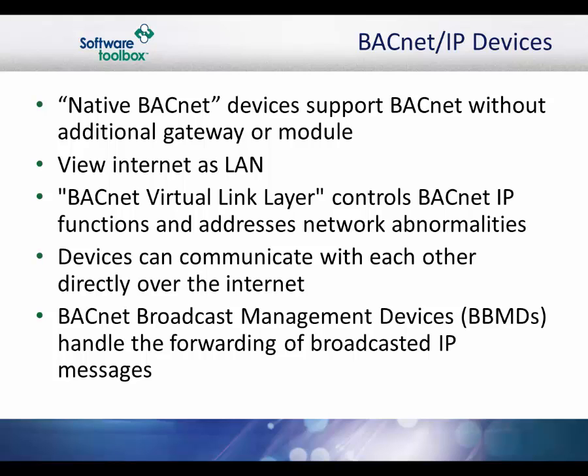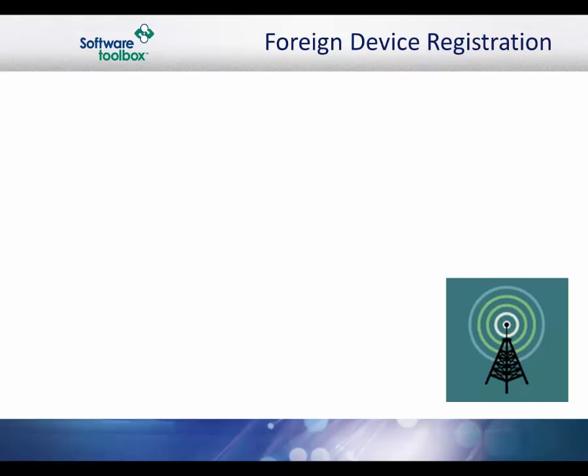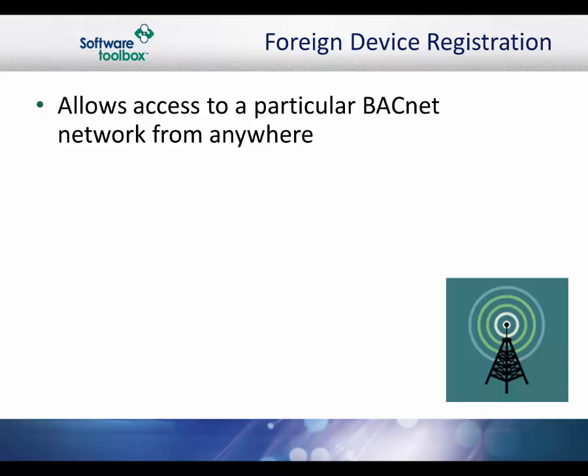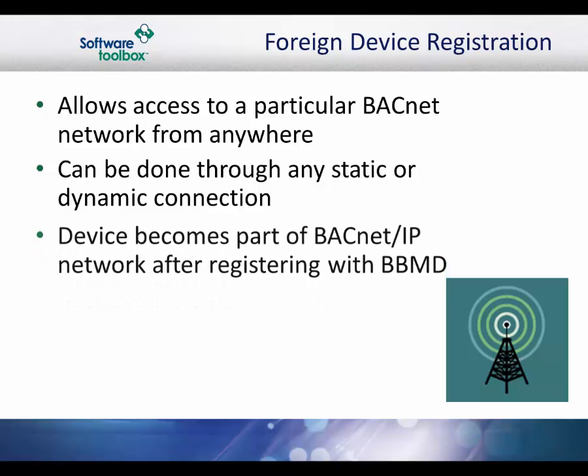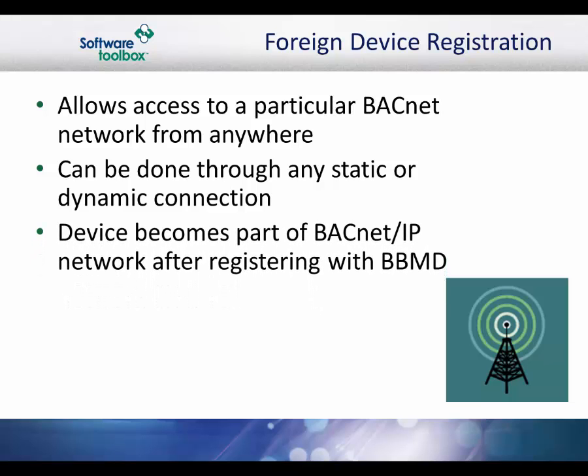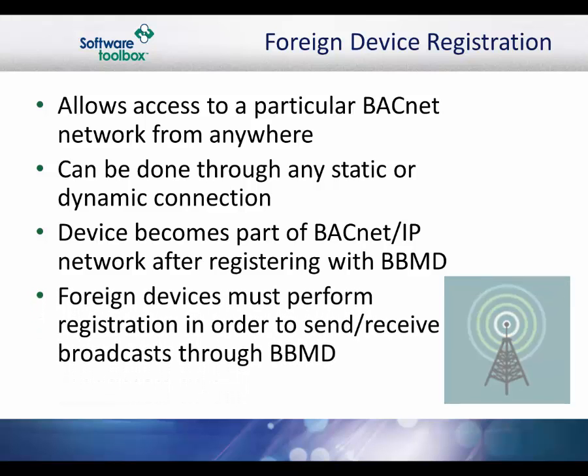In order to access a particular BACnet network from anywhere, foreign device registration was developed. Foreign device registration can be carried out through any static or dynamic internet connection. By registering with a BACnet broadcast management device, or BBMD, the workstation becomes a member of the BACnet IP network and receives forwarded broadcast messages from the BBMD when they are available, and can request that messages be broadcast by the BBMD on its behalf. The foreign device can talk with any BACnet device directly without registration, but will only receive broadcasts if the registration procedure is performed.